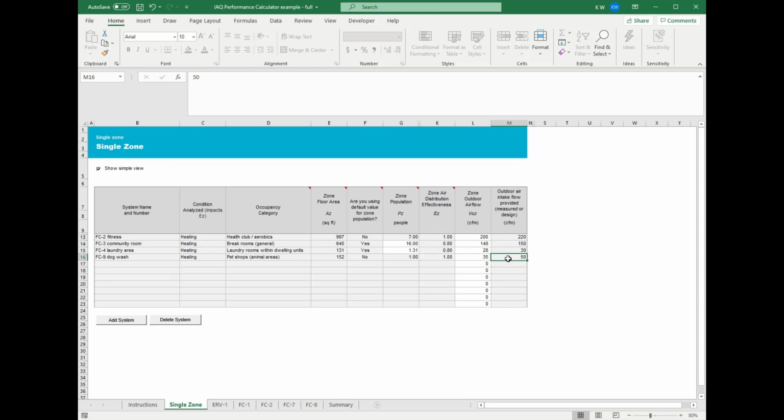And it really has to match the plans and the mechanical schedule. One of the most common mistakes I find is that the values that are here don't match the mechanical schedule. And that's obviously a mistake. And sometimes that's a version control problem, but sometimes it's just one person inputting the values here and that's not the same person who's actually doing the designs or something along those lines. So we can get discrepancies. So these values have to match.